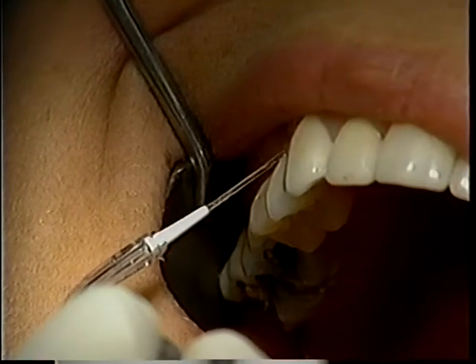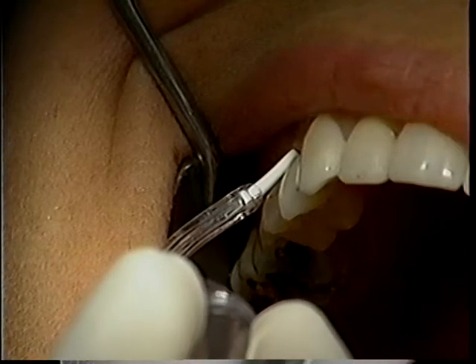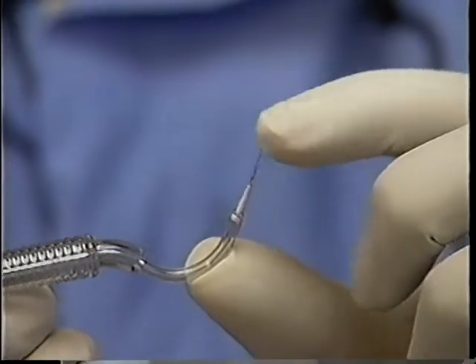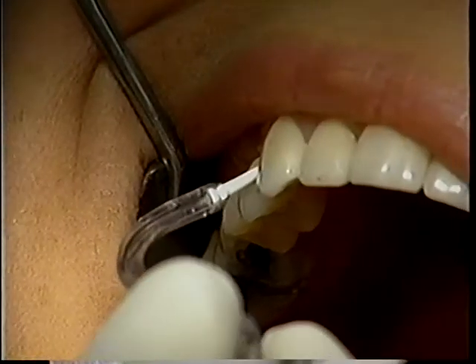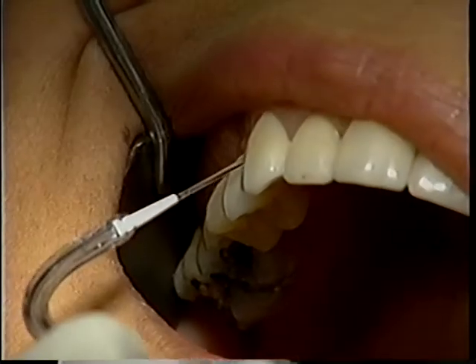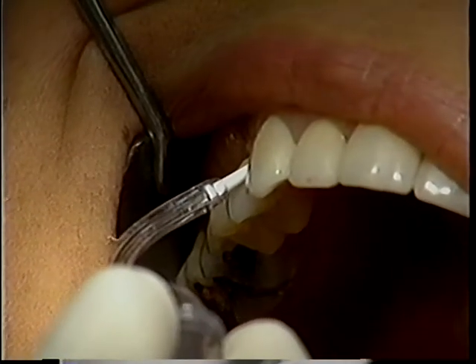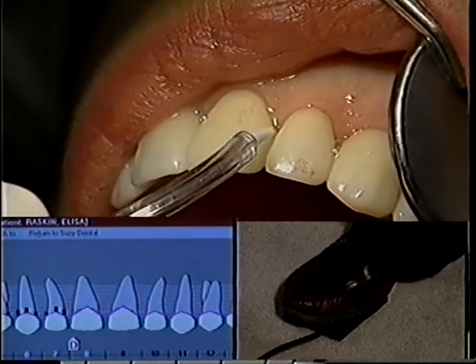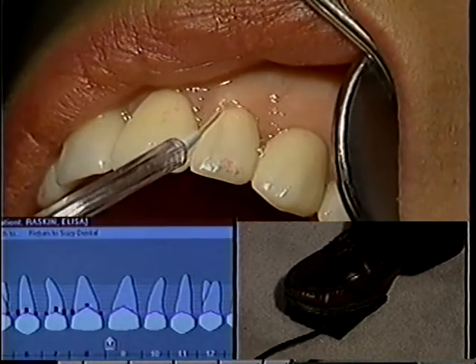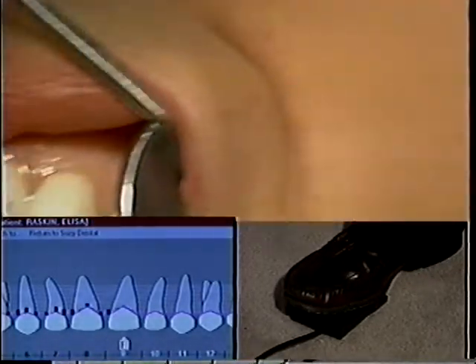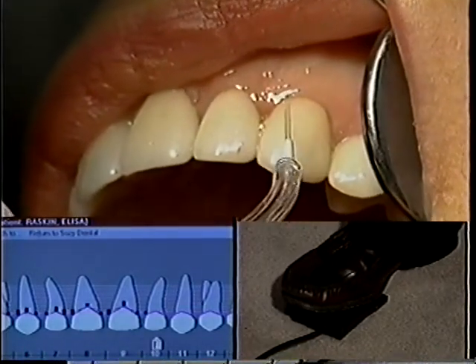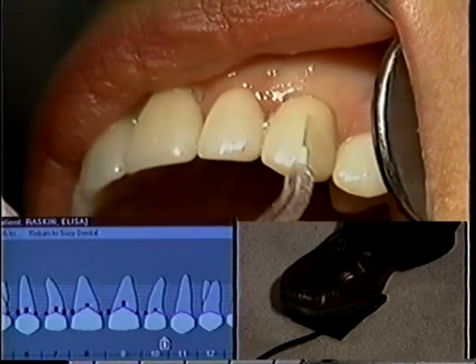With the Probe One, it's very critical you do not rely on a tactile sense that you are accustomed to, but instead learn to depend on visual feedback of the white sleeve making contact with the gingival crest. Through eye, hand, and foot coordination, you'll learn to tap the pedal at the instant you see the contact made, and thereby you'll get an accurate result quickly and efficiently. If you do not use this visual approach, it's very likely that you will fail to obtain accurate measurements.